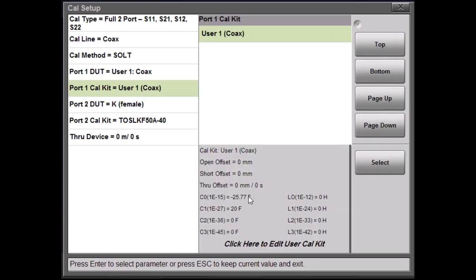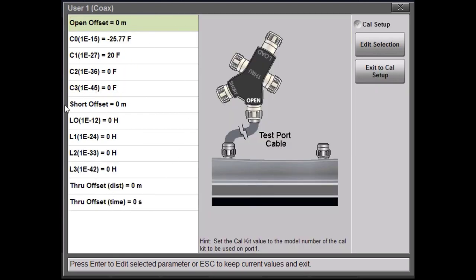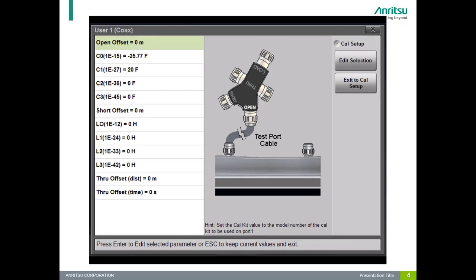Now I'm going to talk about each of these settings and why they're important and how they affect your calibration. The first parameters I want to cover are the offsets. There are three offsets — for the open, short, and thru essentially: the open offset distance, the short offset distance, and the through offset distance. The offset distance, also known as length, is probably the most important factor when entering your user-defined calibration kit. After that, there are correction factors for the open, which is the capacitance, and the correction factor for the short, which is the inductance.